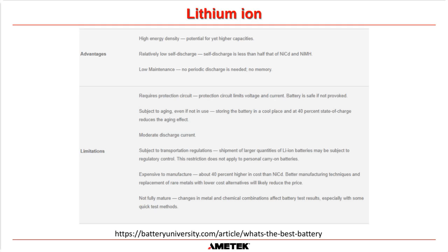Lithium-ion, the advantages: high energy density. And because the technology is new, there's potential for yet higher capacities for smaller size. So the technology is always getting better. So you get much better energy density for a lithium-ion battery. They also have relatively low self-discharge rates, and they're very low maintenance. In fact, no periodic discharge is needed. There's no memory effect.